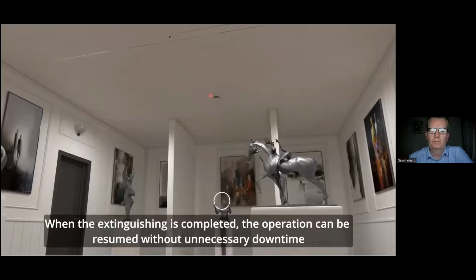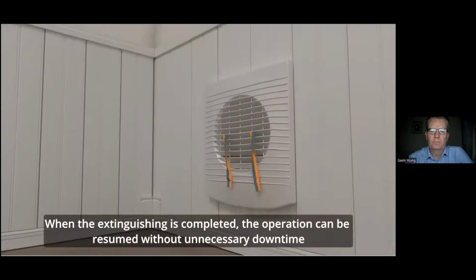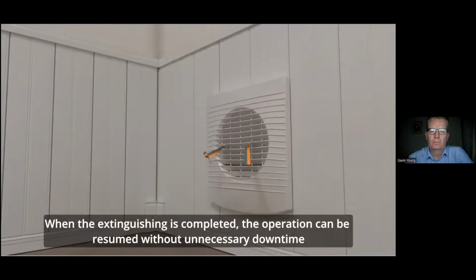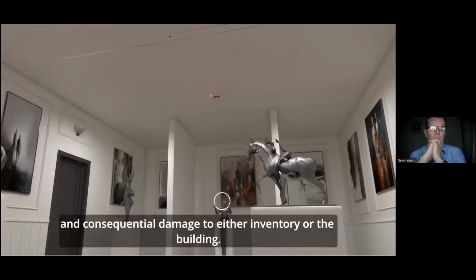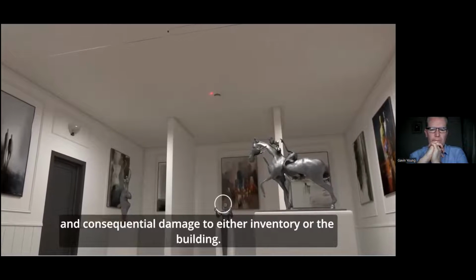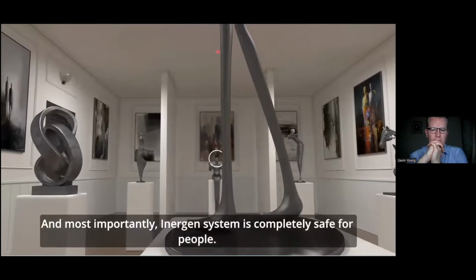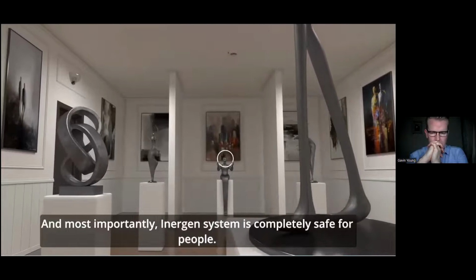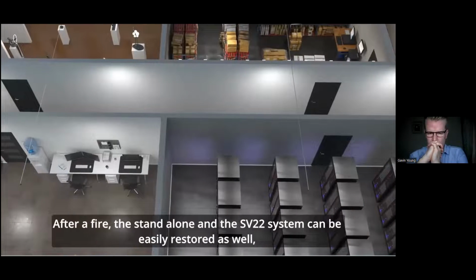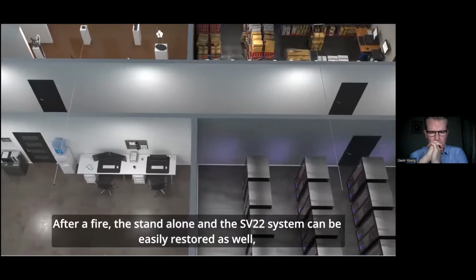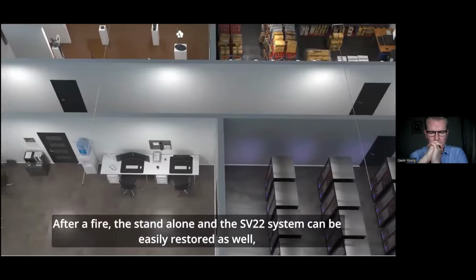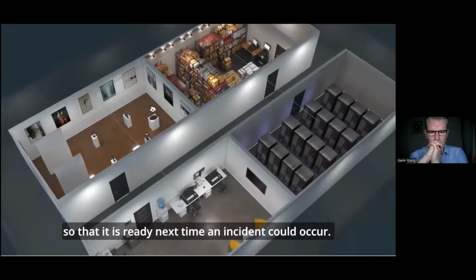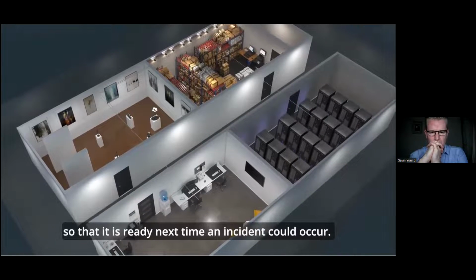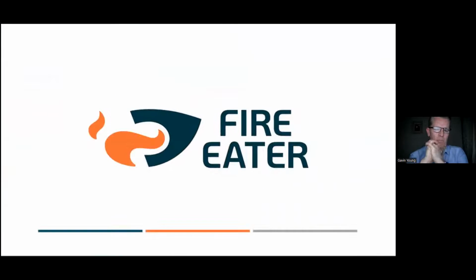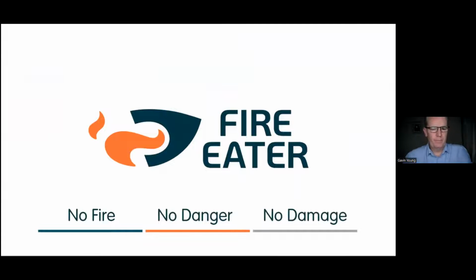When the extinguishing is completed, the operation can be resumed without unnecessary downtime and consequential damage to either inventory or the building. And most importantly, the Inergen system is completely safe for people. After a fire, the standalone and the SV22 system can be easily restored as well, so that it is ready next time an incident could occur. Fire eater. No fire, no danger, no damage.